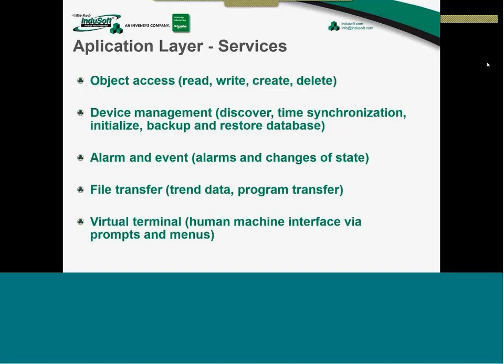Another thing that is interesting on the Bacnet protocol is that it has a lot of services. Object access, for example: read, write, create, delete. You can create objects inside the Bacnet. The device management, like discover, time synchronization, initialize, backup, restore database. We'll talk a little bit more about the discover. That is one of the greatest services that Bacnet has. Alarm and event, file transfer, and virtual terminal.